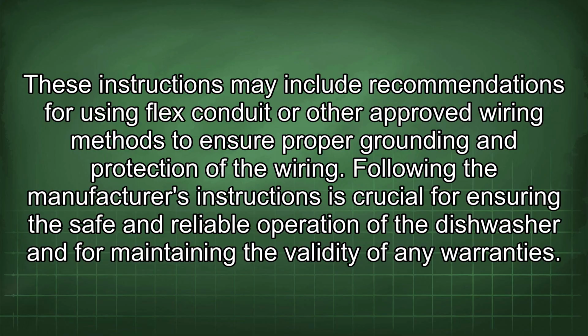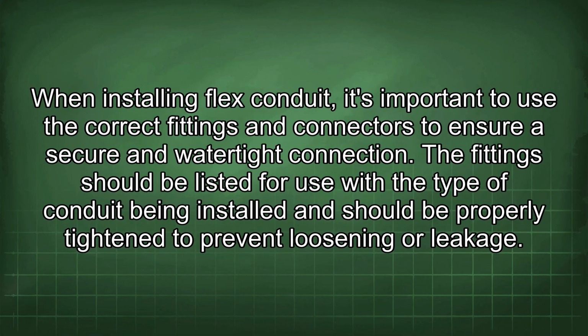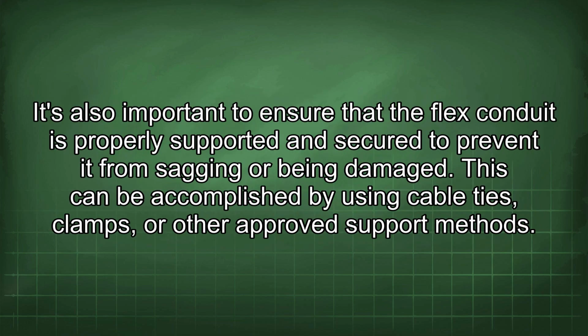When installing flex conduit, it's important to use the correct fittings and connectors to ensure a secure and watertight connection. The fittings should be listed for use with the type of conduit being installed and should be properly tightened to prevent loosening or leakage. It's also important to ensure that the flex conduit is properly supported and secured to prevent it from sagging or being damaged. This can be accomplished by using cable ties, clamps, or other approved support methods.